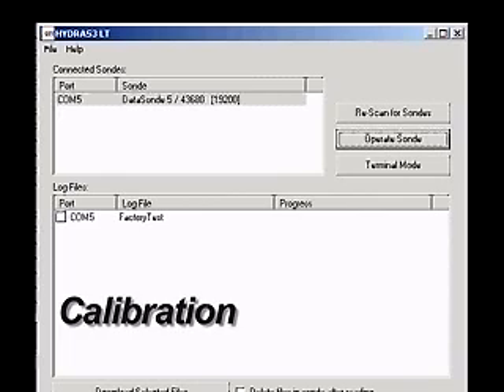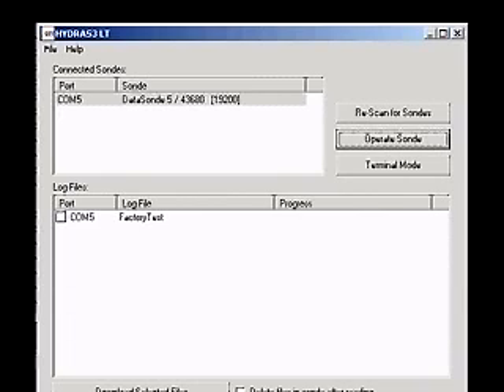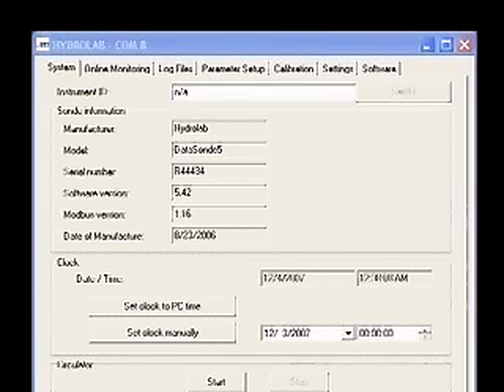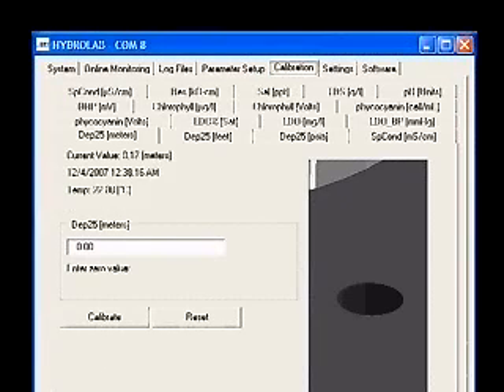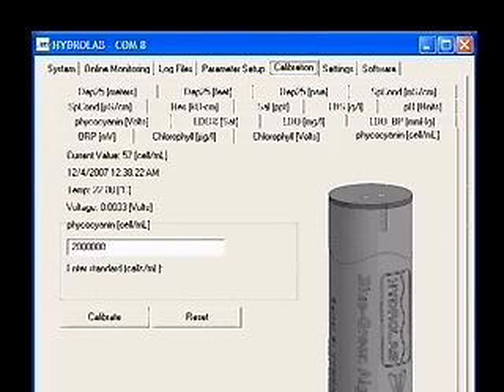Calibration. Establish a connection to the sonde with HYDRAS3LT. Click the button labeled Operate Sonde. When the sonde finishes its initialization, click the Calibration tab. Then click the Phycocyanin cells per milliliter tab or Phycoerythrin cells per milliliter tab. You will see a picture of the fluorometer as well as the current cells per milliliter, the date and time, the current temperature, and the voltage reading of the sensor.